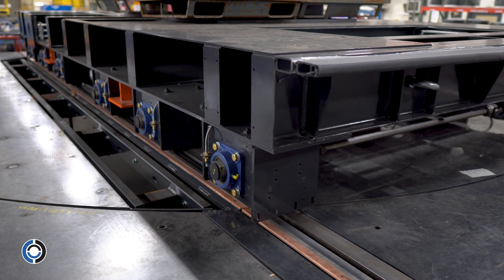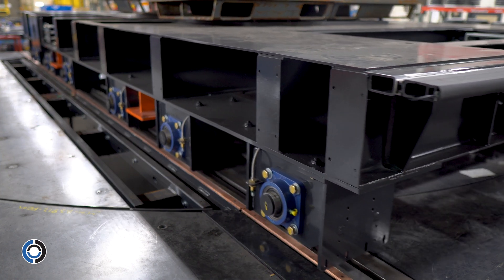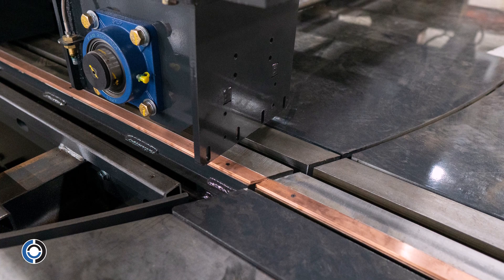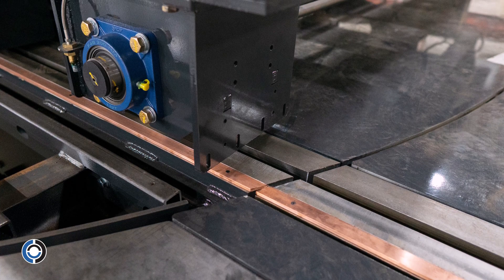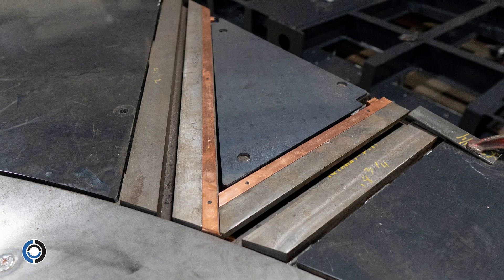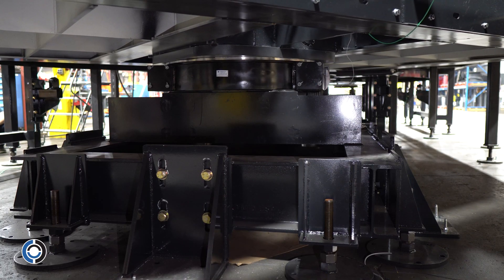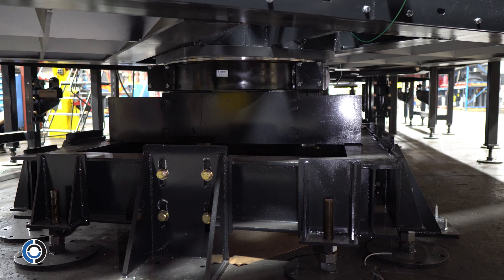The products being transported on the carts and turntable system are sensitive to static electricity, meaning we had to implement grounding bars with less than one ohm of resistance between any point on the grounding bars to the main grounding lug. A slip ring is used to connect the grounding bars on the rotating turntable top to the fixed base.